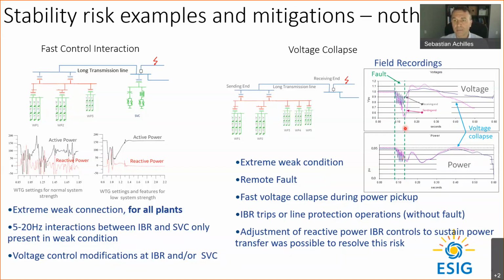At the time of clearing, because the active power from the turbines is lower, the voltage in the system gets significantly high, right? So you have a weak system with significant capacitance. If you reduce the amount of power you're pushing, the reactive power consumption in the system is lower, and for that reason, when you clear the fault, you're pushing less power, the voltage gets really high. Nothing new there, perfectly stable, no problem with that.